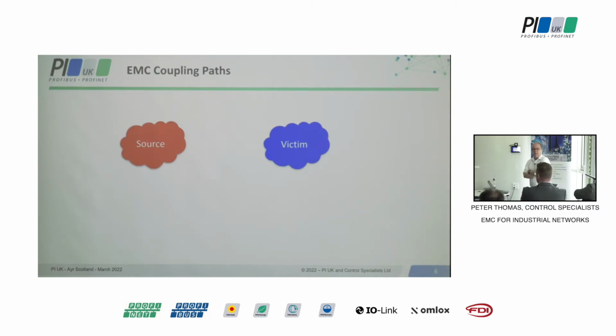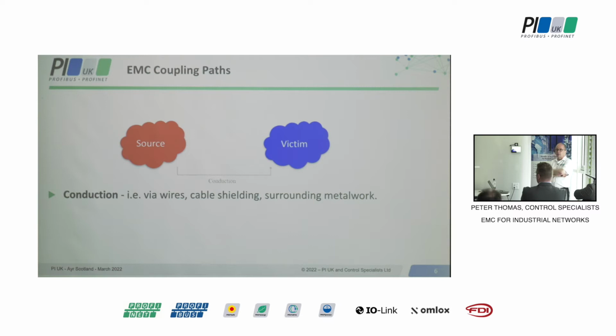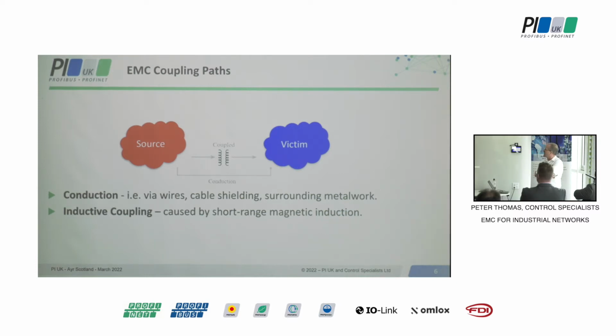There are a number of ways that interference can get from a source to its victim, and not all of them are applicable to the world we work in. There's conduction, where coupling happens via the wires or the bonding infrastructure between source and victim. There's also near-field coupling, within a few meters, either inductive, caused by fast changing currents, or capacitive, caused by fast changing voltages. If you consider yourself a 50-60 hertz person, then by definition voltage and current are changing at the same speed, so you must have both. But in drives it's slightly different, and we're going to emphasize one of those two as a potential issue.